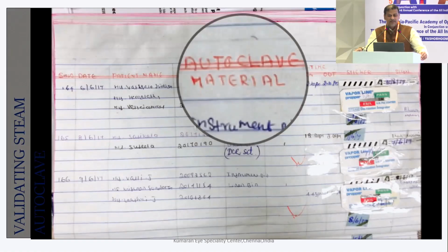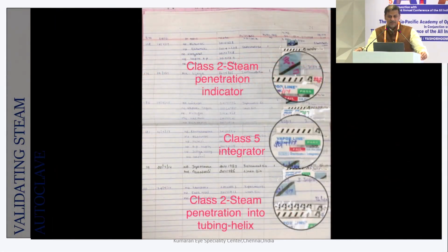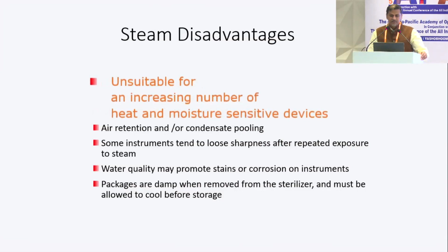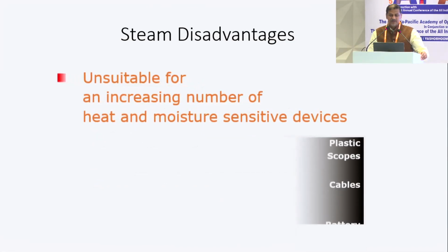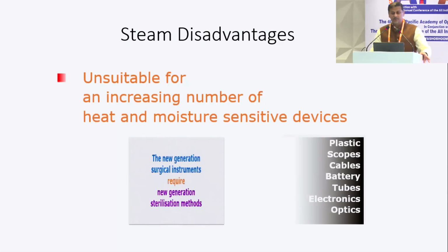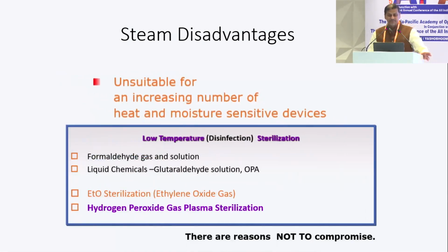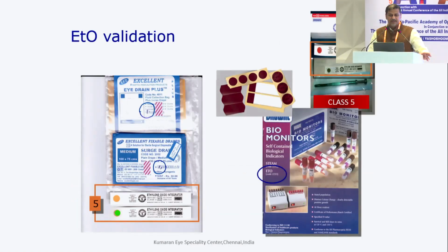Then whatever said and done, make sure you have a proper validating and recording technique where all the indicators are stuck on the tubes. So steam does have disadvantages because it cannot sterilize all this. For this we use ETO and plasma indicators. And ETO, as I told you, has a different validation sticker, so don't use your steam validation stickers for ETO.